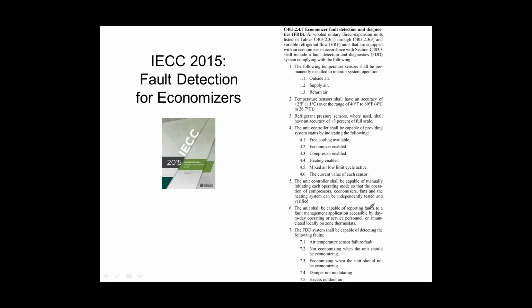Specifically, the hang-up is this one right here, number 6. I have to report the faults to a fault management application accessible by day-to-day operating or service personnel, or annunciated on a local thermostat, right? So if I've got a DDC system and I'm going to text or email alarms out to people, great, done, no problem. If I've got a simple job that has a 5-ton rooftop unit with a thermostat, what the hell am I supposed to do, right?